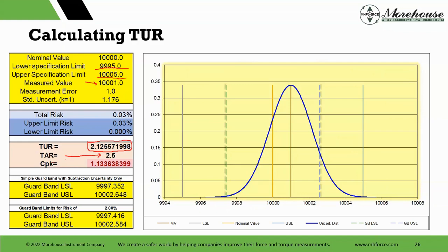You could start looking at things when you do not take measurement uncertainty into account, when you do not do other things. Typically TAR is going to be a constant because you're not using resolution, you're not using repeatability. And then this pesky little CPK thing, and that detects the location of the measurement, which I'm going to talk more about.